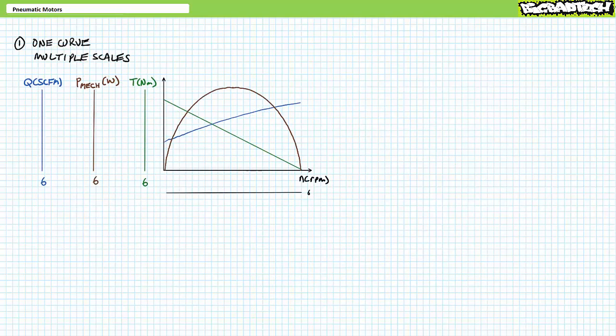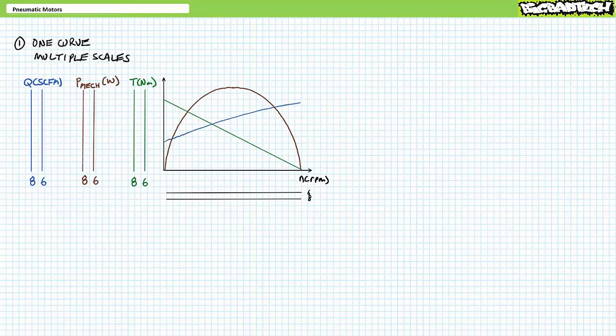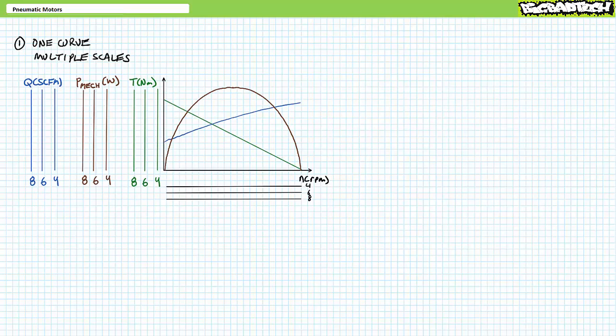Method one uses one curve per property and multiple scales for different load-induced pressure conditions. This method is based on the fact that the previously discussed combined chart is valid only at a specific load-induced pressure, let's say 6 bar. If load-induced pressure is 6 bar, use the 6 bar scale. If load-induced pressure increased to 8 bar, one would use the 8 bar horizontal and vertical scales that appear parallel to the scales at 6. Similarly, if load-induced pressure dropped to 4 bar, one would use the 4 bar scales. This method is workable, however a little confusing because you've got to remember to use the right scale, and the datasheet may not illustrate the exact load-induced pressure of interest, so you've got to do some extrapolation.